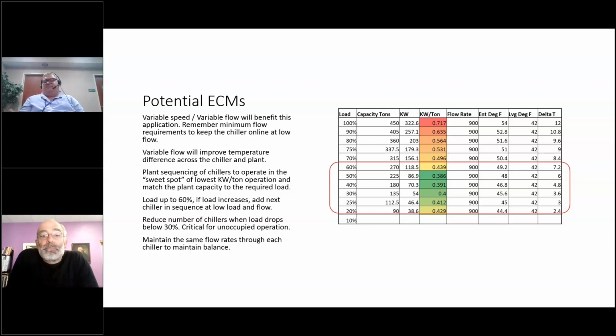Yeah, but they all look like this, all at constant flow rates. They don't look at the ECM potential of maintaining a constant delta T. Keep a constant delta T and you'll run the most efficient chiller. It automatically dials in to maintain that delta T wherever your flow falls.